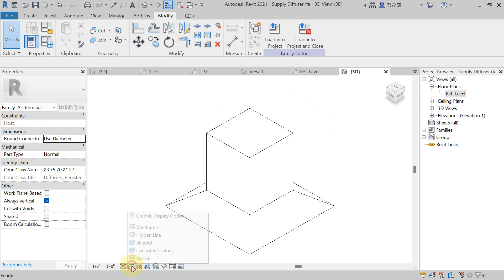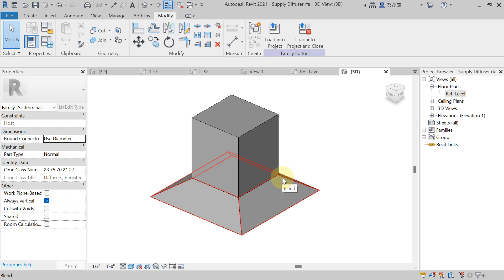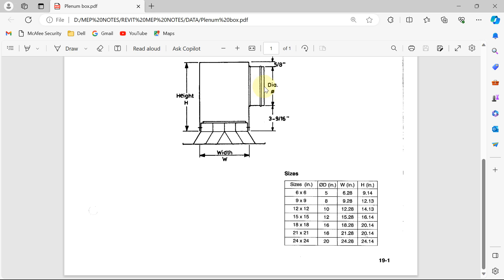You can see the result in 3D shaded view — we have created the plenum box body. Now we need to create the circular opening on top to connect the duct. The opening diameter is 10 inch. If you want to connect a rectangular duct to this round opening you can use a rectangular-to-round fitting. From the catalog, for a 12 by 12 inch neck size the opening offset from the base is 3 and 9/16 inch, which calculates to 3.5625 inch, and from the top it is 5/8 inch, which is 0.625 inch.